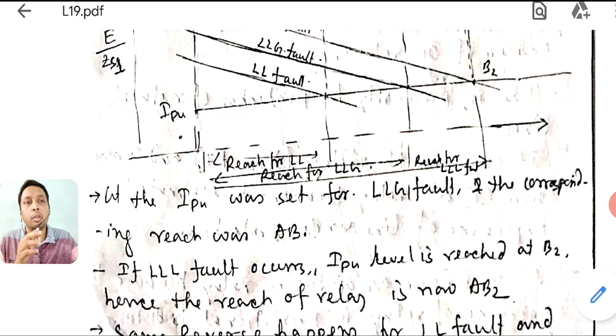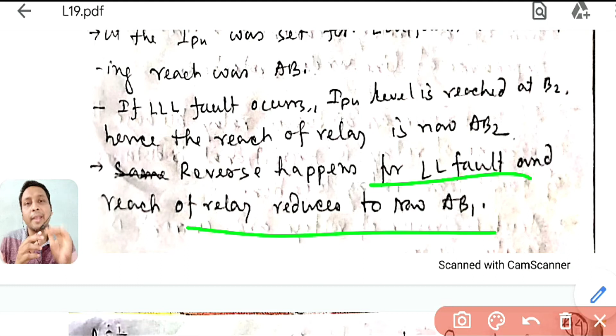Here you can see IPU was set for double L G fault. The corresponding reach is AB. For triple L, it overreaches, now going to AB2. And the reverse happened for double L fault. For less severe faults, it reduces to AB1. Even below double L, there is an LG fault. It will further reduce. The reach will further reduce.